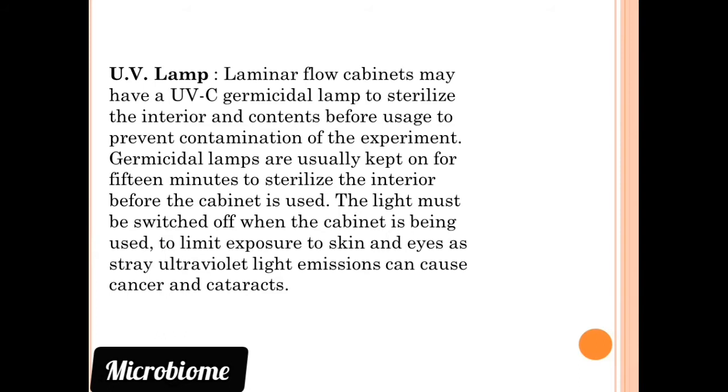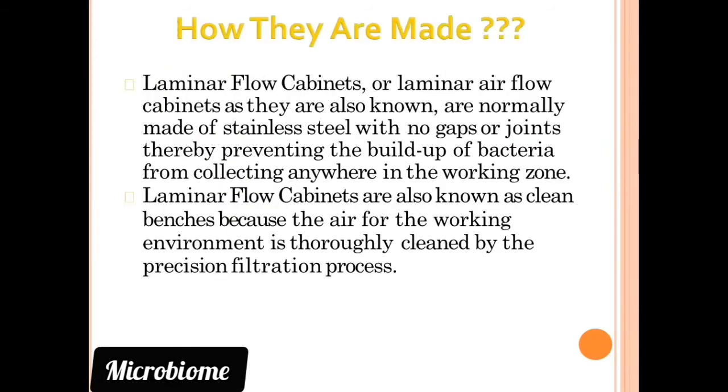The light must be switched off when the cabinet is being used to limit exposure to skin and eyes, as stray ultraviolet light emissions can cause cancer and cataracts. So before working you have to switch on the UV light lamp to maintain the sterile condition.